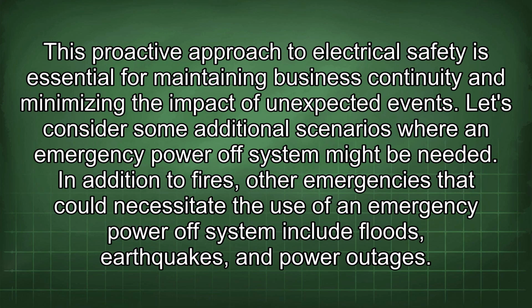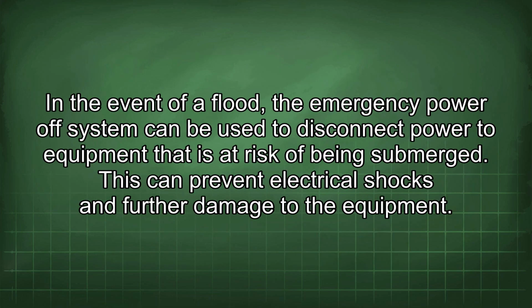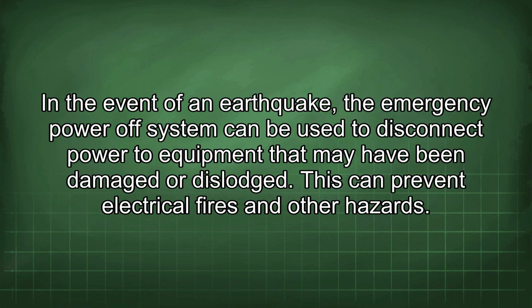In addition to fires, other emergencies that could necessitate the use of an emergency power-off system include floods, earthquakes, and power outages. In the event of a flood, the emergency power-off system can be used to disconnect power to equipment that is at risk of being submerged. This can prevent electrical shocks and further damage to the equipment. In the event of an earthquake, the emergency power-off system can be used to disconnect power to equipment that may have been damaged or dislodged. This can prevent electrical fires and other hazards.